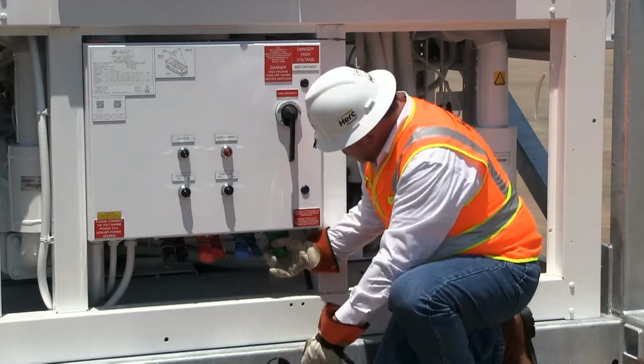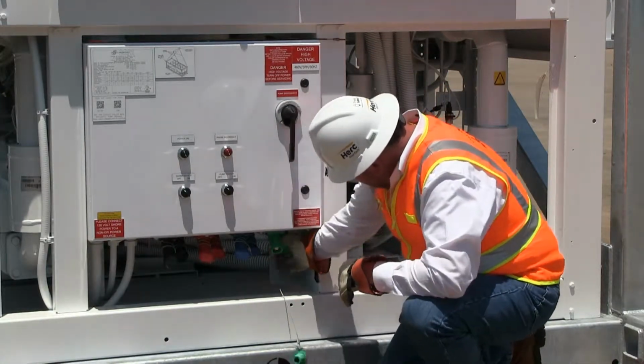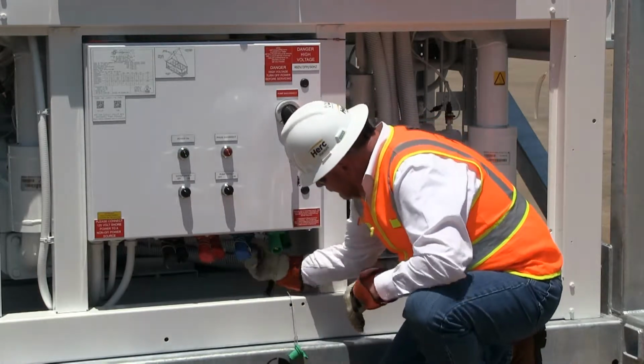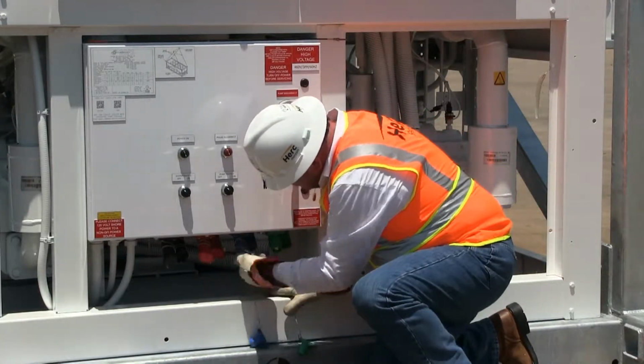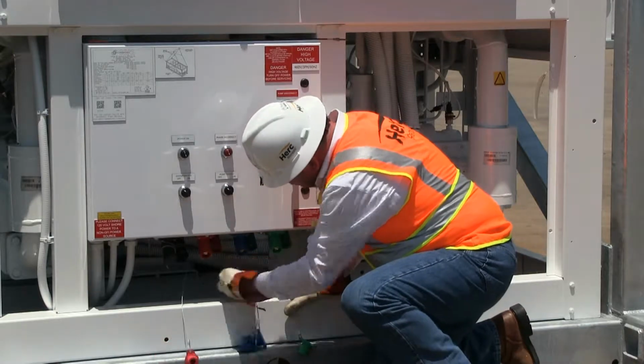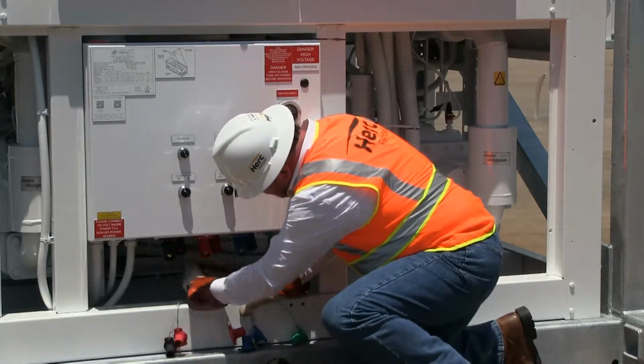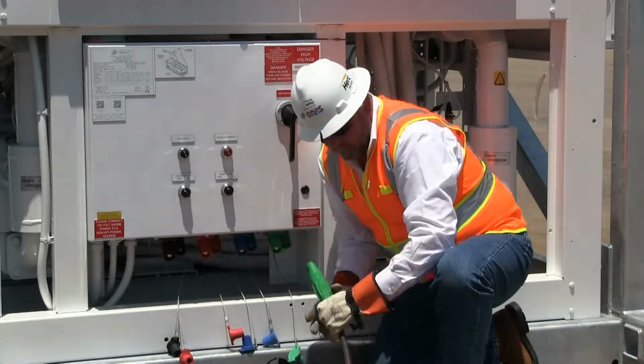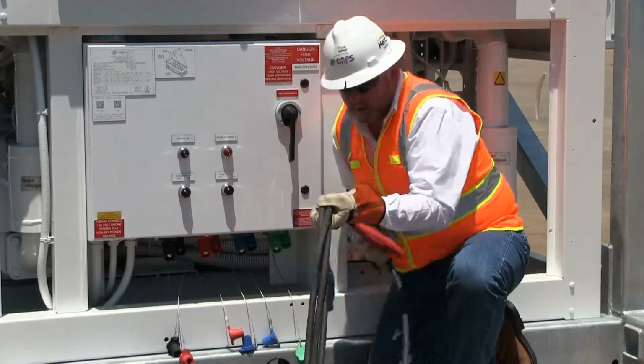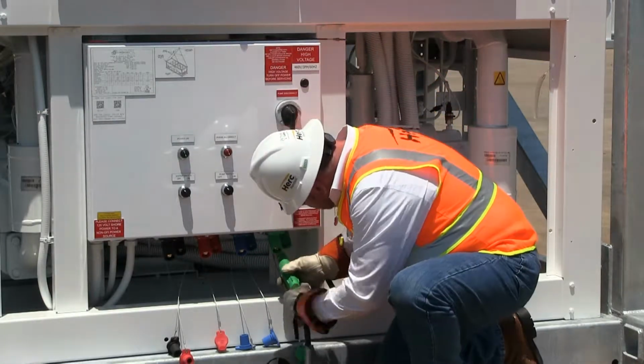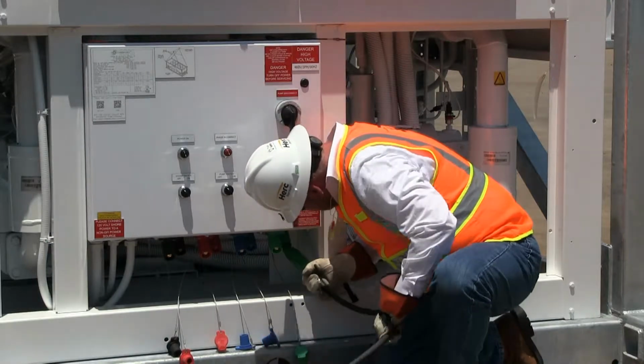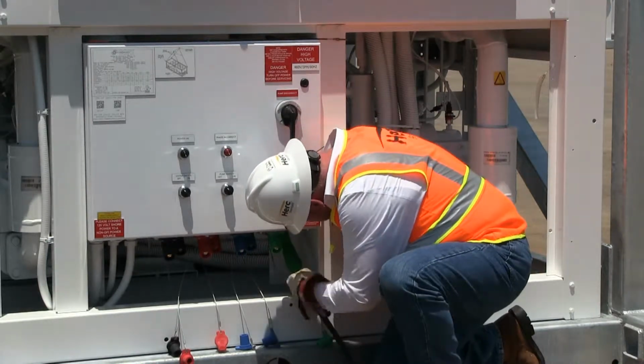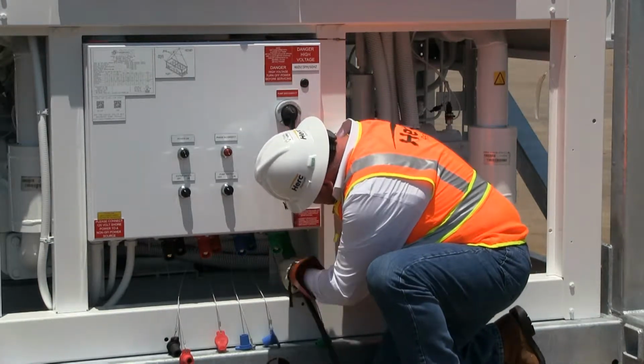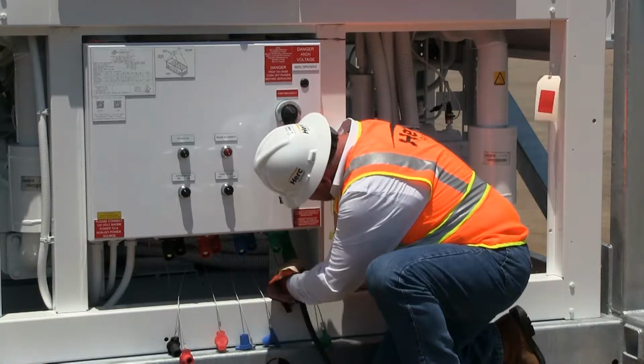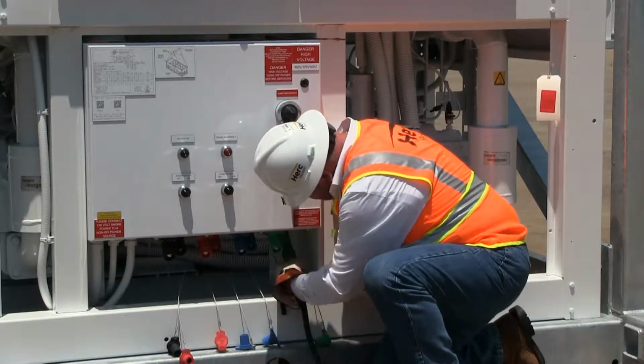So I'm going to start by removing the dust caps and the moisture shields here off the Camlocks. And you'll notice we've got two sets. They're back to back and they are offset, so it makes it easier to hook them up. We're going to hook up the first set of Camlocks, and you're always going to hook up your ground first. That's for safety. We're going to go to the back set here, and we're going to hook up the ground first, and then proceed with L1, L2, and L3.